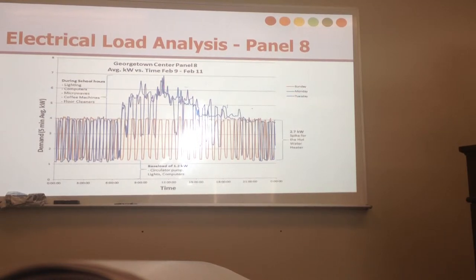Just two days during the week, they fluctuate a little bit, but they're pretty consistent Monday to Friday when people are in the building. Again, you can see when people get there in the morning, they turn on the lights, computers, coffee makers, and then at break time around 9, 9:30, a couple toasters maybe, coffee makers, microwaves, that kind of thing would be causing the spike. And then around lunchtime, again it'd be your fridges, microwaves, coffee makers, same thing. Everyone in the staff room, that'd be all your lighting. And then as people go back to class or go back to their office, it spikes down a little bit. Then maybe afternoon break, they come back, make another coffee, open the fridge a couple times, a couple more spikes. And then as you can see, it keeps dipping down as people go home for the day. And then maybe these couple spikes would be at the end of the day, the custodian or the janitors are in, putting the floor cleaners going, causing a couple spikes.